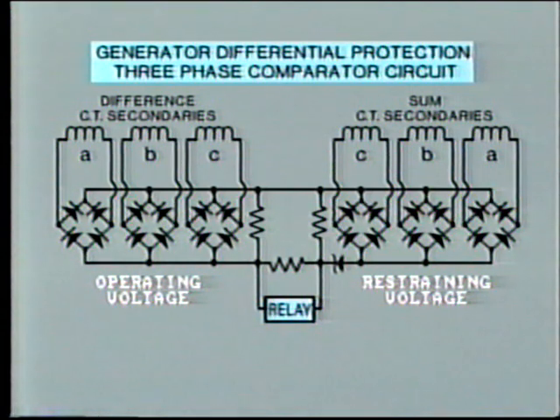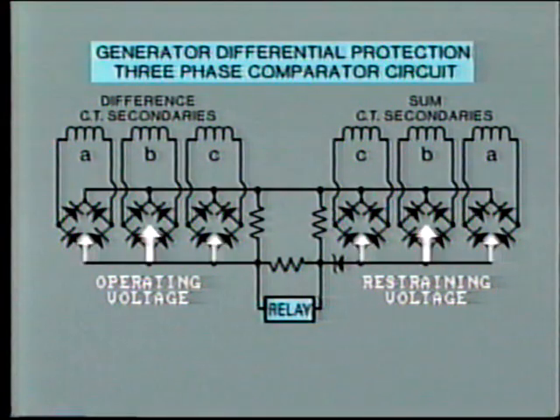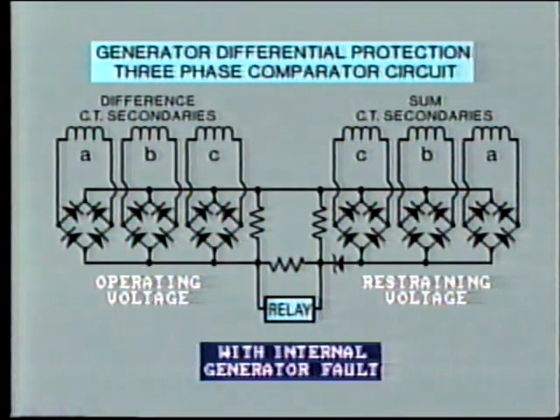At any particular instant, the DC voltage present will be the highest of the three phases on either side of the relay. An internal generator fault will provide a high voltage signal on the differential side and a low restraint on the summation side. The result will be a trip of the relay.